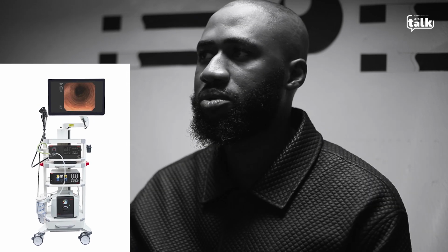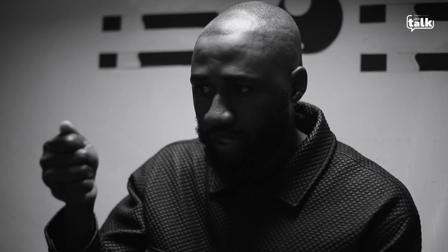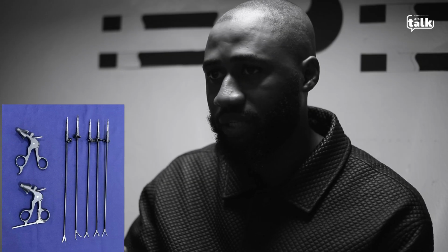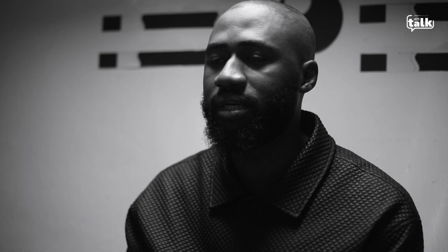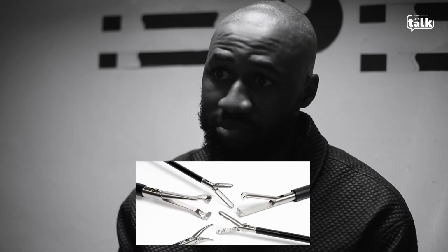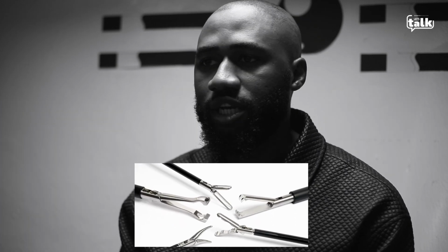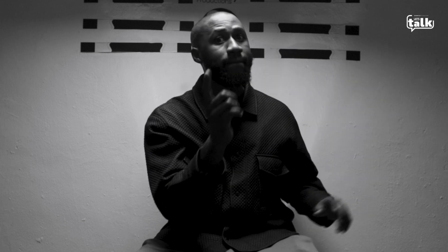And the laparoscopy, on the other hand, like I said earlier, is just the use of the telescope. You need the telescope, you need a trocar, you need laparoscopic scissors, those are the cutting scissors, and a grasper. Those are the instruments you need, and that's it. You also need the full stack that I mentioned for the endoscopy. So the difference is you just plug a pigtail to the insufflator, and that's it.